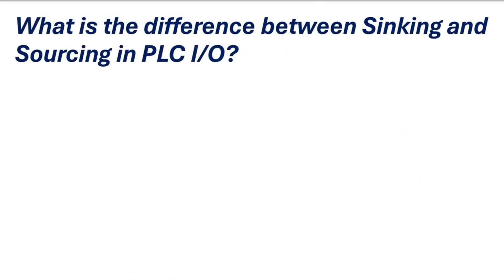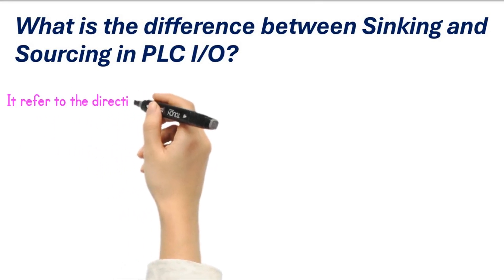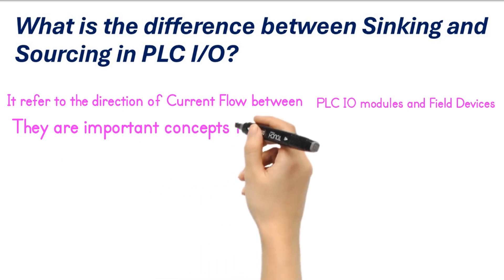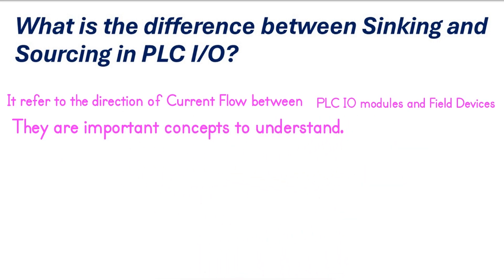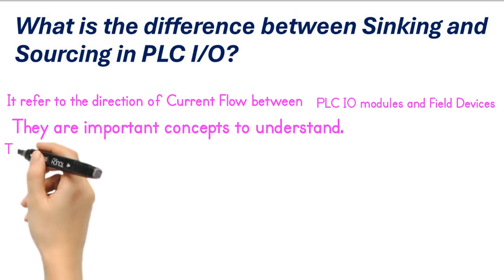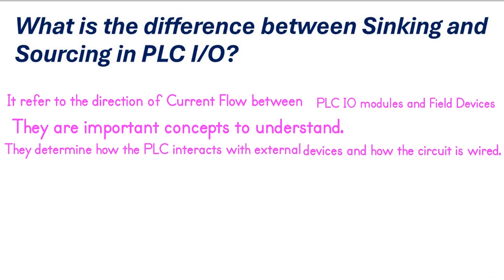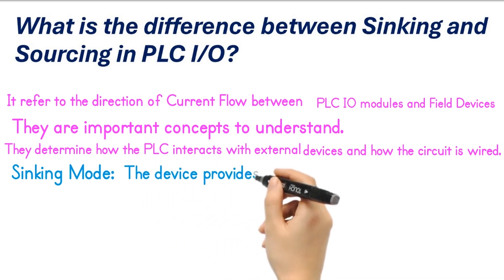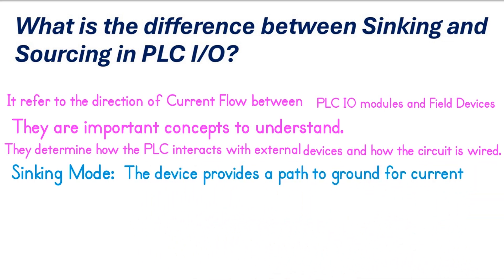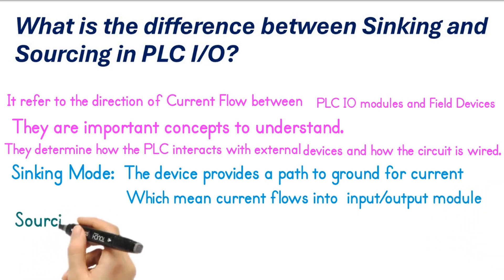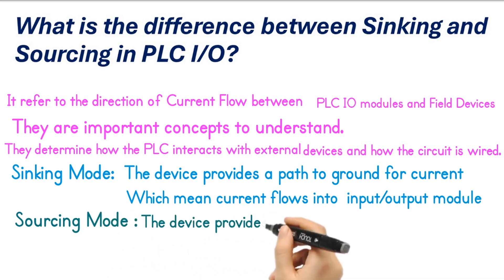What is the difference between sinking and sourcing in PLC I/O? Sinking and sourcing refer to the direction of current flow between a PLC I/O module and an external field device. These are important concepts when working with PLC I/O modules, as they determine how the PLC interacts with external devices and how the circuit is wired. In sinking mode, the device provides a path to ground for current, meaning current flows into the I/O module. In sourcing mode, the device supplies current to the I/O module, meaning current flows out of the module.